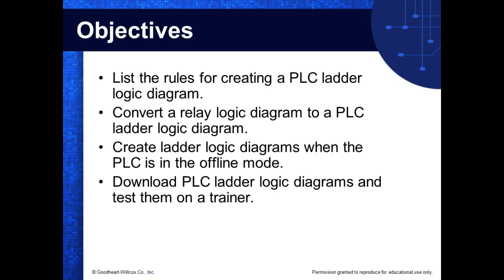So you're going to either upload the program or download it: upload it from the PLC into your computer, or download it into the PLC. Now that's backwards from the internet, right? You understand? So we download it to the PLC, we upload it from the PLC into the memory. So we can take a program that's inside the PLC and upload it back into our programming application, or we can take a program, modify it, and then download it back into the PLC.